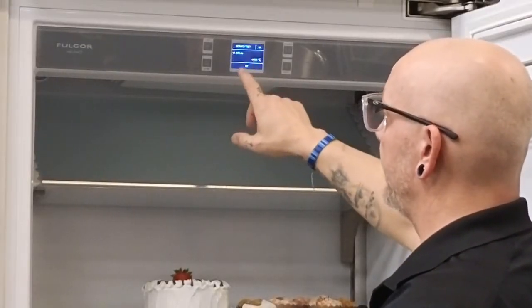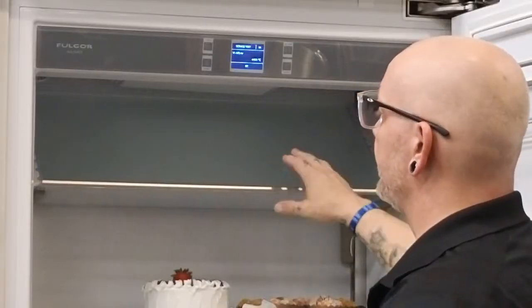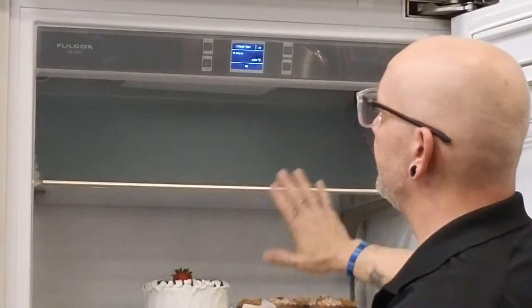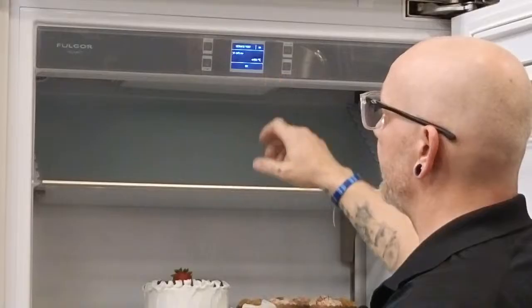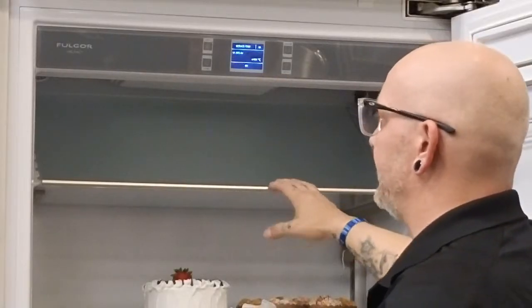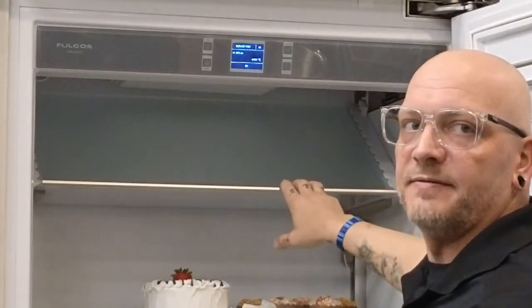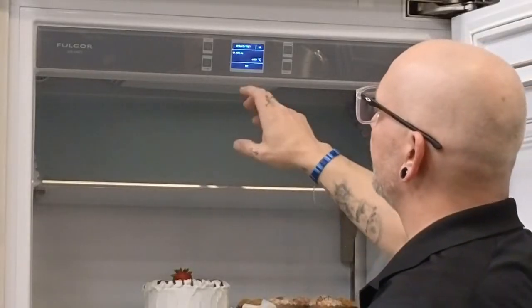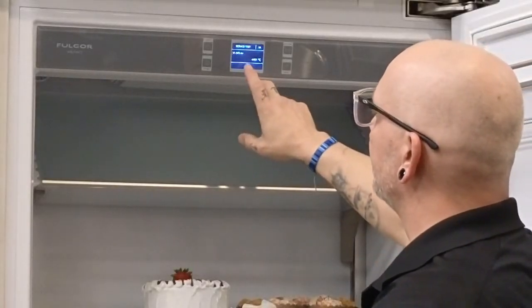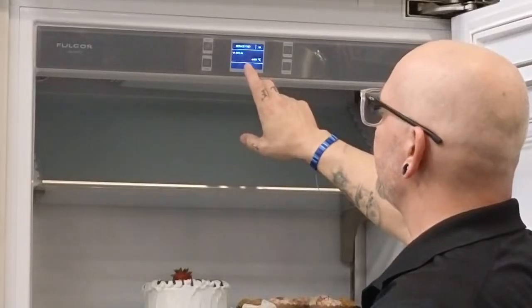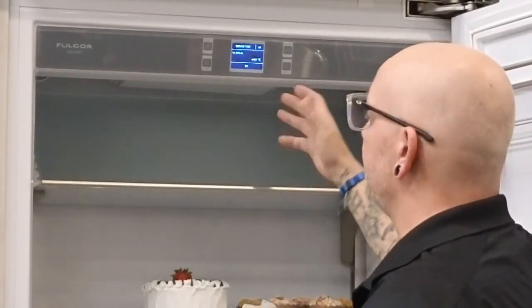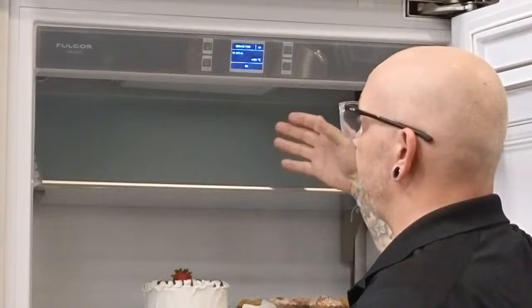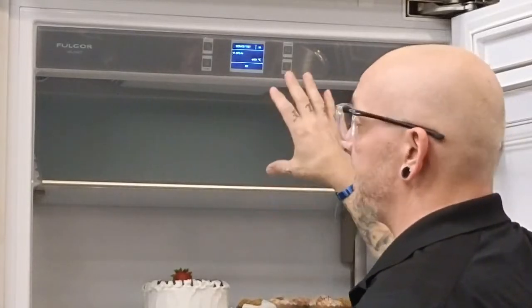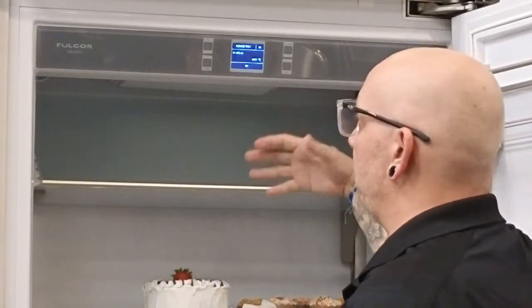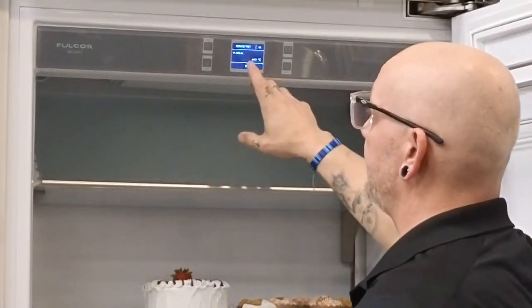And we got V1 NTC air sensors now. So this is the V1 section, fresh food. So the air sensor is reading positive 20 Celsius. Shiloh, do you know what that is in Fahrenheit off the top of your head? 68. So that makes sense because we've had the door open for quite some time. We shut the compressors down because we put it into demo mode, and then we took it out of demo mode. So that makes sense for it to be right around that temperature.